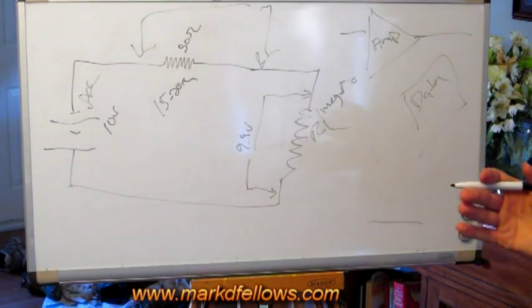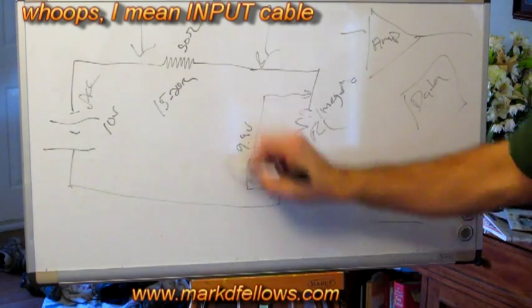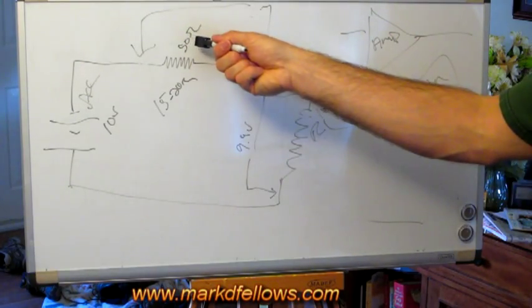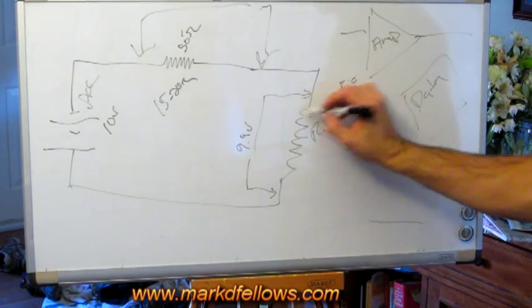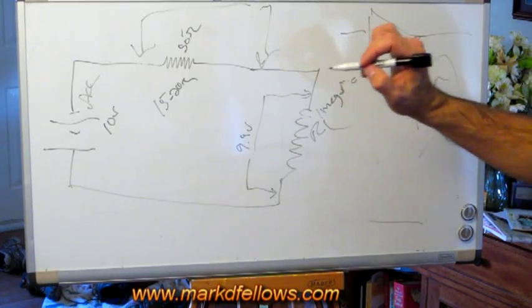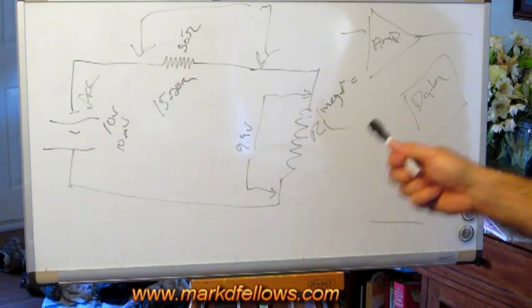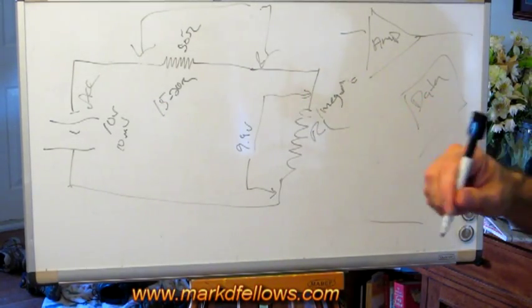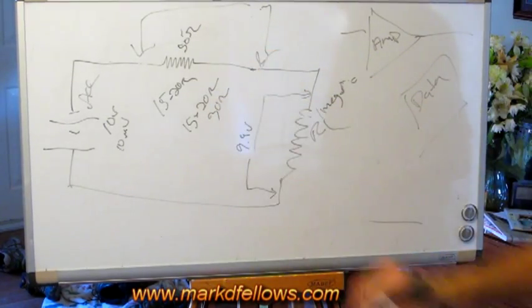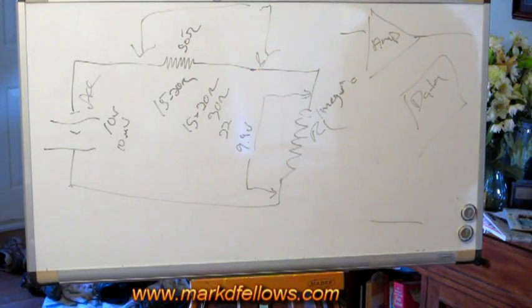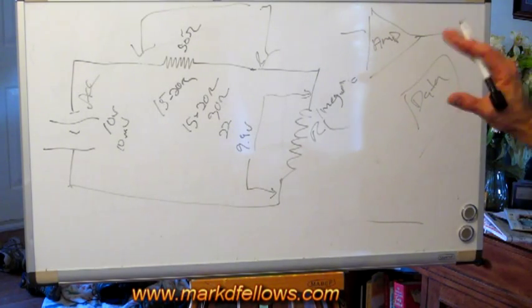So, taking that circuit, that transmission cable, and knowing that your data acquisition system has an input amplifier that's supposed to be infinite resistance, you know that it's going to develop almost all your signal across the input of that amplifier. So, this value becomes less critical. Now, 50 ohms is higher than I'd want in this cable. I mean, in theory, you'd want this to have no resistance, so all of your signal developed across your load resistor. But, it's not as critical. Now, this actually produces, this might produce 10 millivolts or less. It might be in the microvolts. So, it does become an issue. However, it's not as much of an issue as you think. So, it doesn't matter, I say 15 to 20 ohms. It doesn't matter if it's 30 ohms, you know, somewhere around that ballpark. I wasn't going to tell them, oh, okay, you need to cut it off at 22 ohms. Because if you understand how this system works, it's not as critical. You just check the cable and you look for opens and stuff.